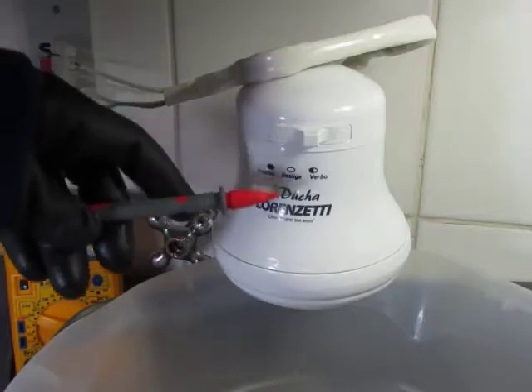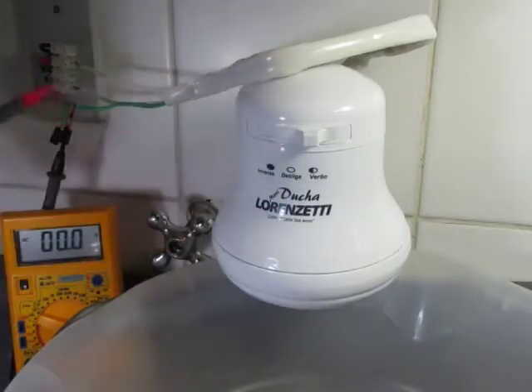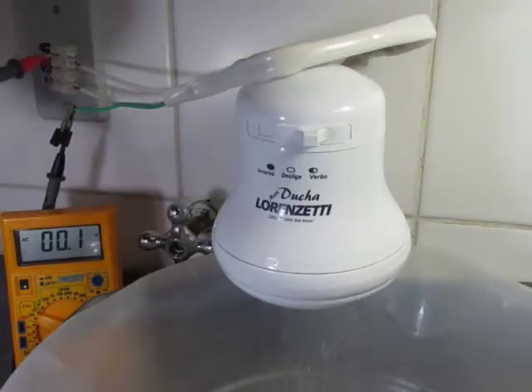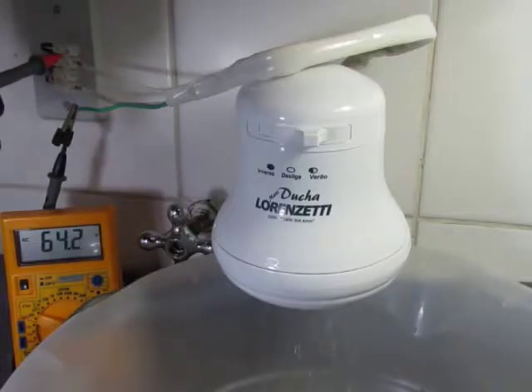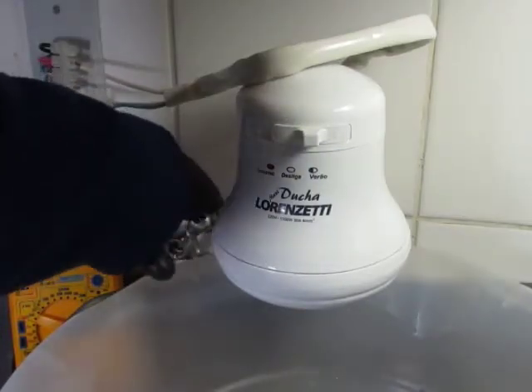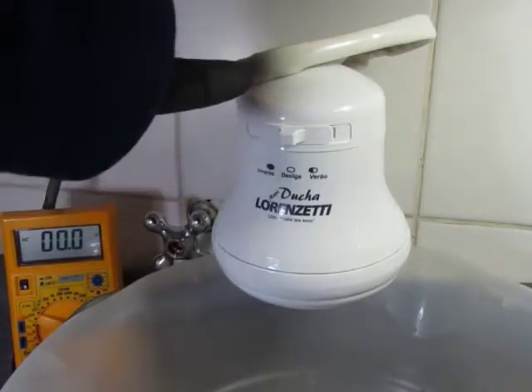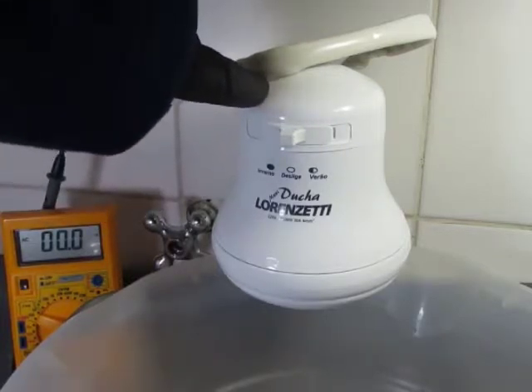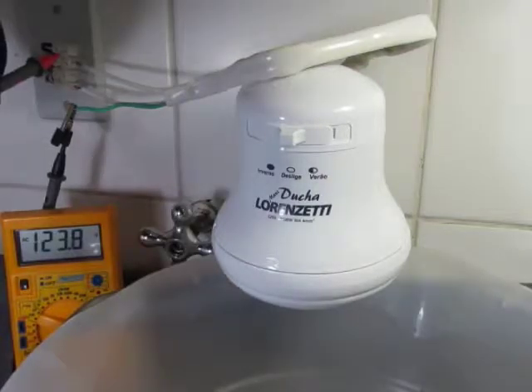So, I will let the water flow with the temperature switch on the low temperature position and I will measure the voltage between the ground wire that is immersed in the water and the mains ground. Water is flowing, it is getting heated and we can see that we have more than 64 volts, quite considerable. We can see that the water is energized. I am going to measure again with the temperature switch on the cold position because we noticed that only one of the contacts of the switch is blocked but not the other, which could convey electrical potential to the heating element and consequently to the water. And there you have it. It is even higher at around 124 volts.